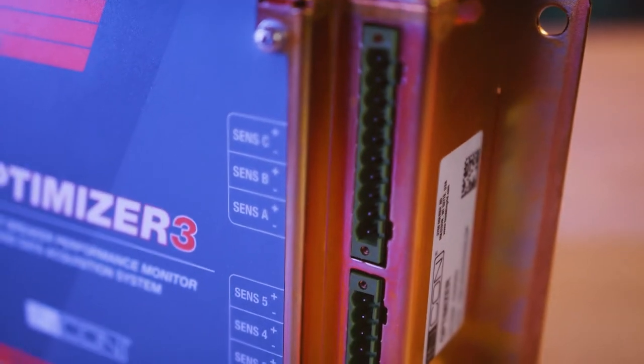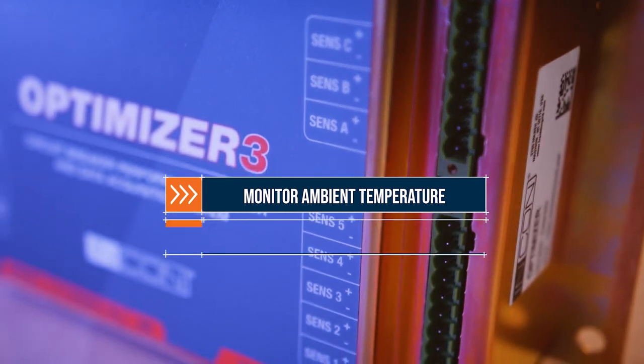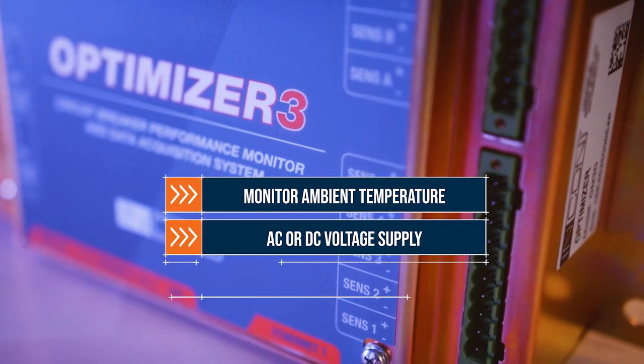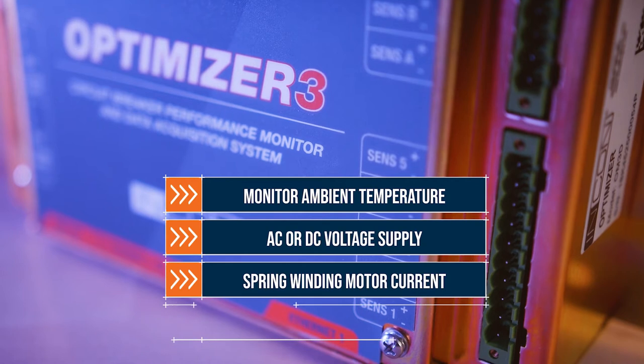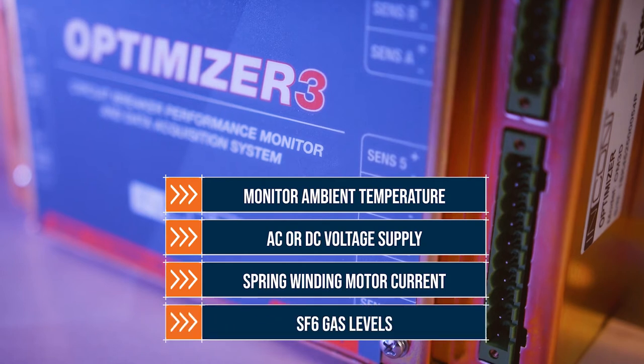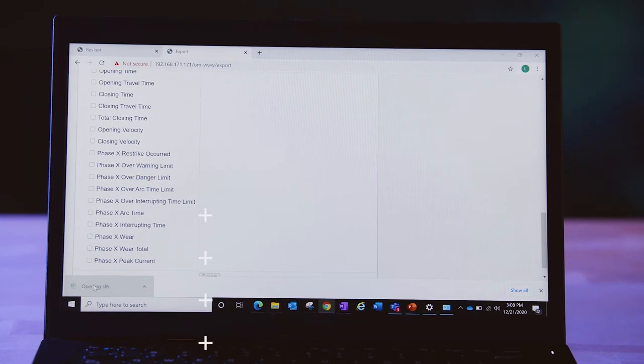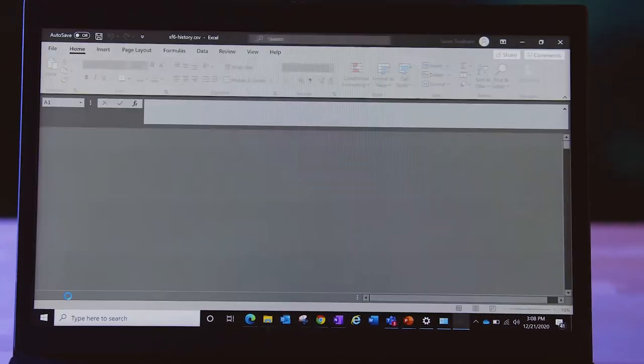Eight sensor inputs also allow you to monitor ambient temperature, AC or DC voltage supply, spring winding motor current, and SF6 gas levels, including gas density, pressure, and dew point, all of which optimizes your ability to generate compliance reports for regulatory agencies.